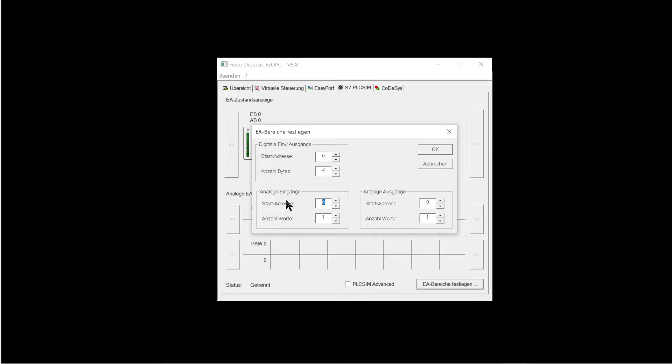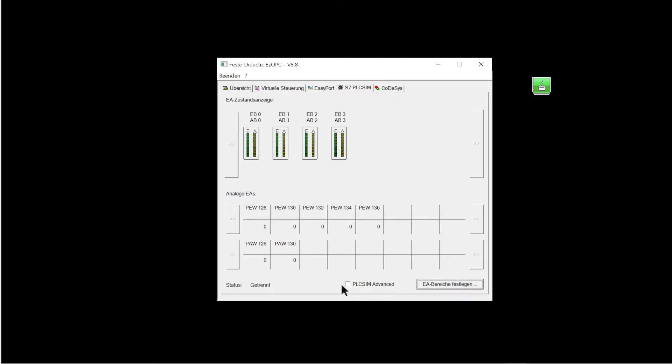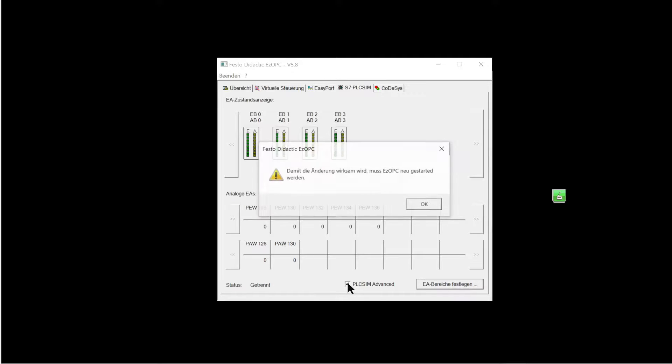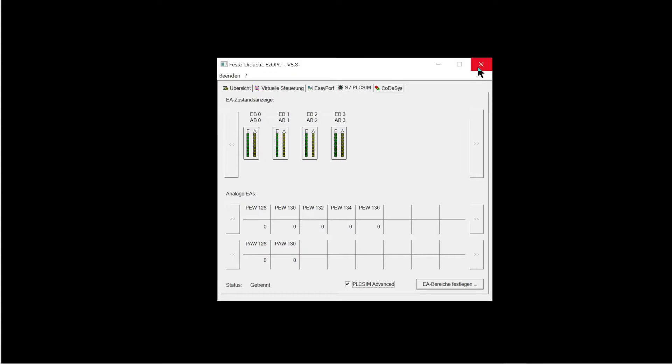When using the analog IO, their start address and the number of words are also entered. The selected controller has five analog inputs and two analog outputs. If PLC Sim Advanced is used, the associated checkmark must be set on the S7 PLC Sim tab. With that everything is set. EZOPC will be closed.